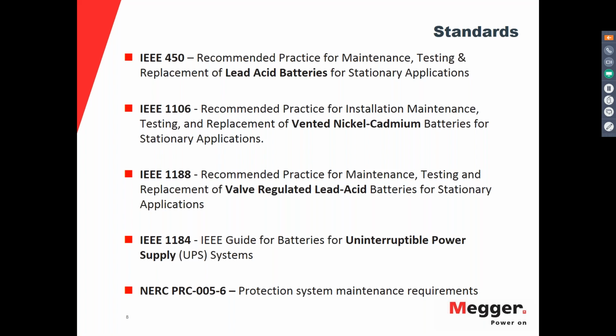Also, in the references here, we have NERC PRC-005, because it is basically a document that most utilities need to follow, and it's a requirement. This regulation asks for, in addition to other maintenance practices, two tests that allow you to verify if the battery is performing to the requirements of the substation. These are the ohmic testing, or the performance test, or the modified performance test. These last two tests, performance and modified performance, are the capacity tests that we are going to be talking about today.